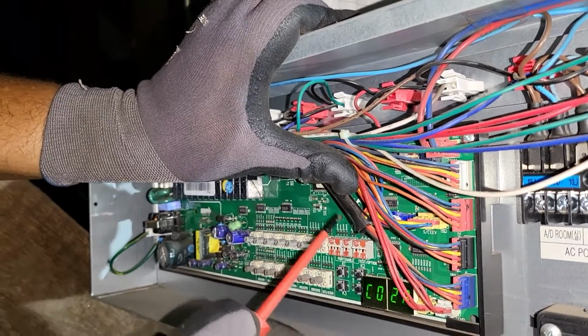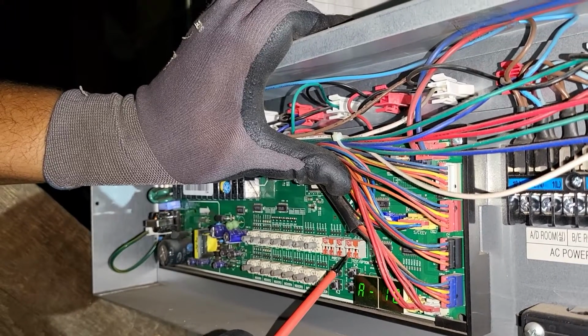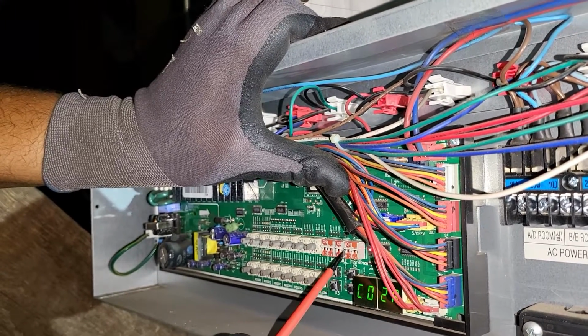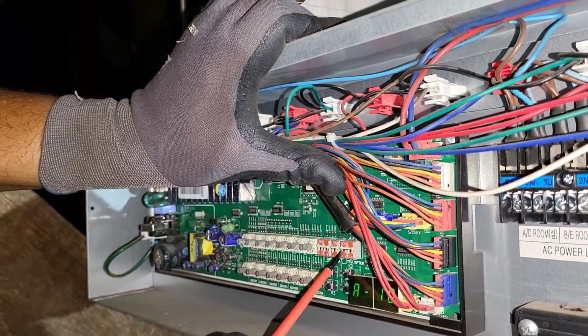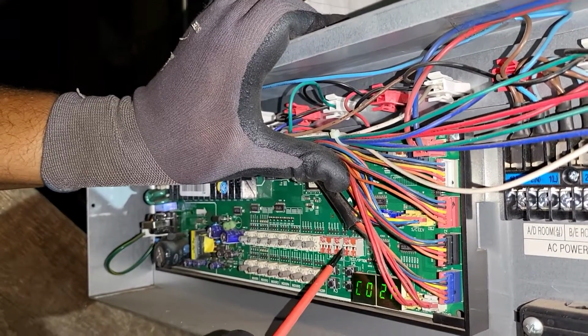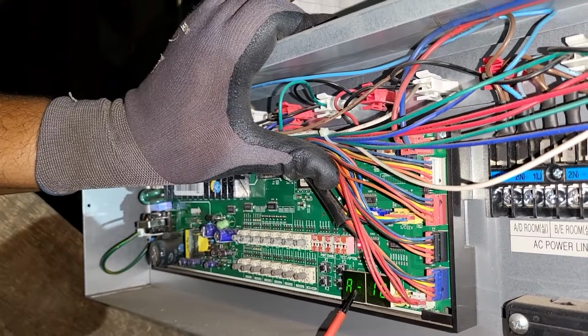That means that ordinarily you would have to have these 2 dip switches in an off position. They are currently in an on position, so that's the first issue we've picked up, and that's a contributing factor towards the E-213 error code.